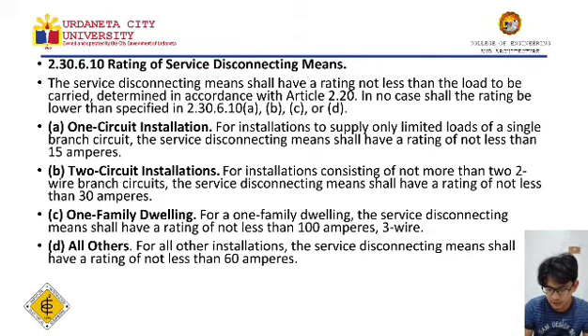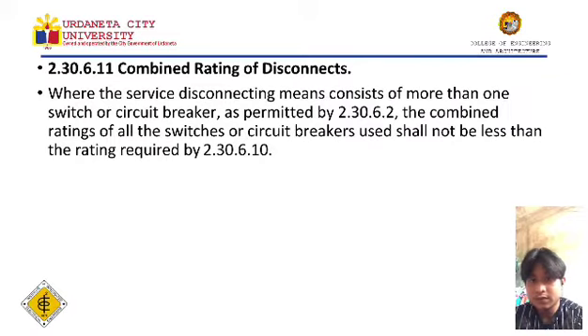For all other installation, the service disconnecting means shall have a rating of not less than 60 amperes. So, yung sa all others daw po, para sa lahat ng iba pang mga installations, ang means of service disconnecting nito ay meron dapat rating na hindi bababa sa 60 amperes. Combined rating of disconnect, where the service disconnecting means consists of more than one switch or circuit breaker as permitted by 2.30.6.2.